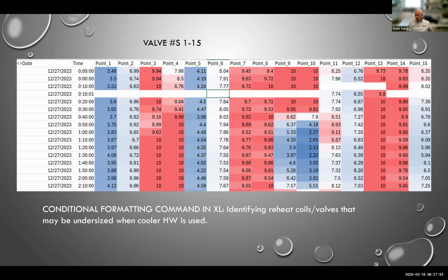So you look at the historical data for the equipment and see its response to heating with higher temperature hot water. And I want to say that the blue boxes were a low voltage, so the valves were not open fully, so they look pretty good. Here we found that many of the control valves wouldn't work, so they're struggling at 10 volts, and it's probable that they need replacement. But one thing is we had to go out and make sure that the valves were actually fully open, even though they had 10 volts. If the valves were sticky, and we've had this problem, the valves might not have been fully open. So it could have been a control valve problem. And so check this before you condemn the coil and valve to be replaced.